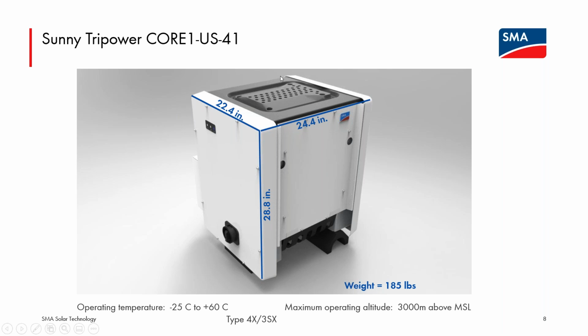So we definitely want folks to leave that airflow path clear. Generally though, if it's very, very cold, some people ask, well, what if snow builds up on the top of the inverter? Generally in that condition, you're worried about the low end of the temperature range versus the high end. But generally we do want that airflow path to remain clear. Even if it's hot air being blown over those heatsink fins, the inverter will manage itself thermally. But generally if there's a bunch of snow sitting on top of the inverter, it's not a question of is it running too hot, but potentially too cold.